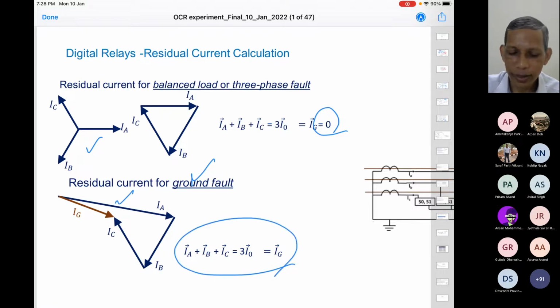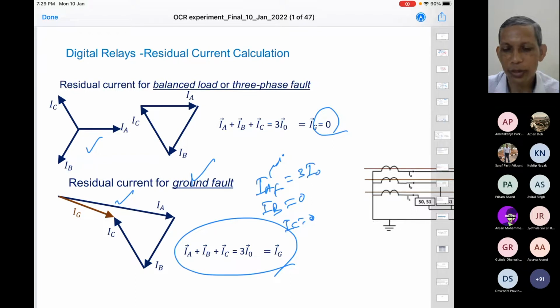Let us say IA, IB, and IC are the three currents. At no load the sum is 0. But now there is a fault here, so IA plus IB plus IC will be equal to 3 times I0. This is called the zero sequence current, and this is nothing but IG, the ground current. I have already elaborated on this earlier. Agree? Or if it is non-zero, some part of it will be compensated, so it will be a little bit smaller.